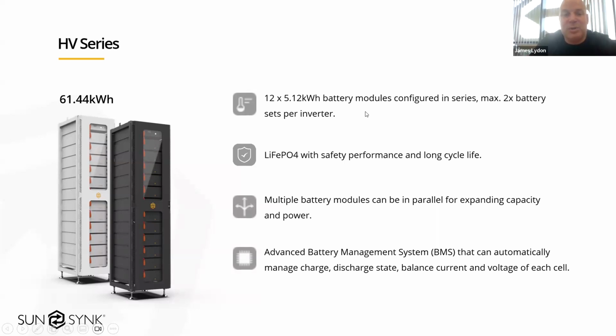The software's been changed now, so we can allow, as I've just mentioned, up to 16. Same lithium iron phosphate, so really safe. All the HV batteries have fire suppression built into all the individual modules. And yeah, like I say, the minimum amount you need connected to each inverter is four. So this cabinet has 12 in, so the full 61.4, but the minimum is four, so just over 20 kilowatt hours of battery storage.